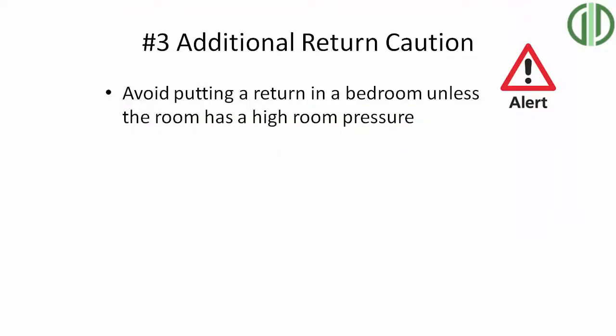Generally, you can't go wrong by adding more returns — we say you can never have enough returns in your home. But be careful installing returns in bedrooms, because you could easily cause an imbalance in the system, making the AC unit work harder and increasing temperature differences. If you put too large a return in a bedroom, you'll cause negative pressure where the door gets sucked closed and the supply doesn't have a chance to cool the room properly. Generally, we want returns in open areas of the house, unless room pressure measurements show at least 15 pascals, which gives a green light to adding a return in a specific bedroom.